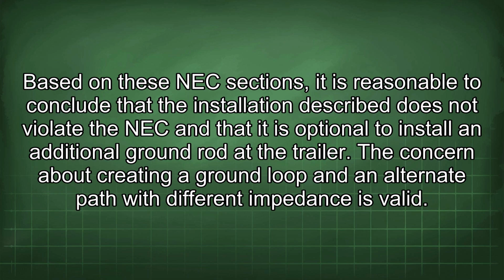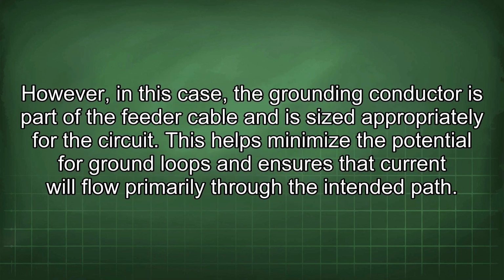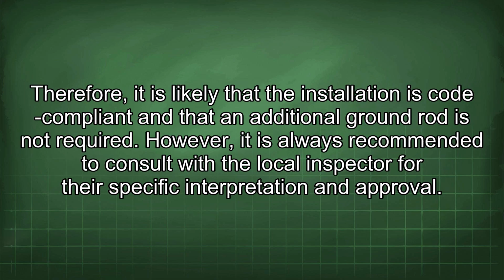Based on these NEC sections, it is reasonable to conclude that the installation described does not violate the NEC and that it is optional to install an additional ground rod at the trailer. The concern about creating a ground loop and an alternate path with different impedance is valid. However, in this case, the grounding conductor is part of the feeder cable and is sized appropriately for the circuit. This helps minimize the potential for ground loops and ensures that current will flow primarily through the intended path. Therefore, it is likely that the installation is code compliant and that an additional ground rod is not required. However, it is always recommended to consult with the local inspector for their specific interpretation and approval.